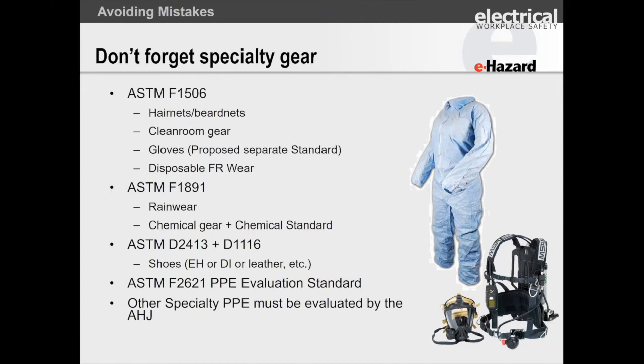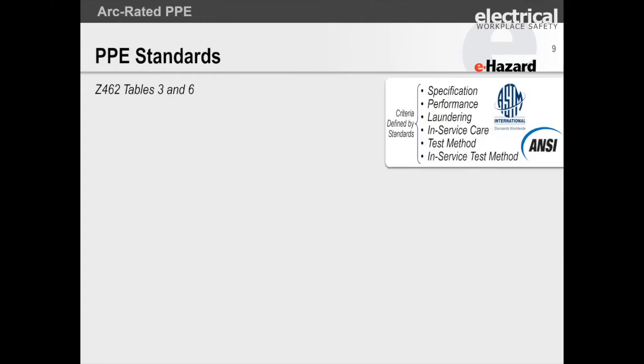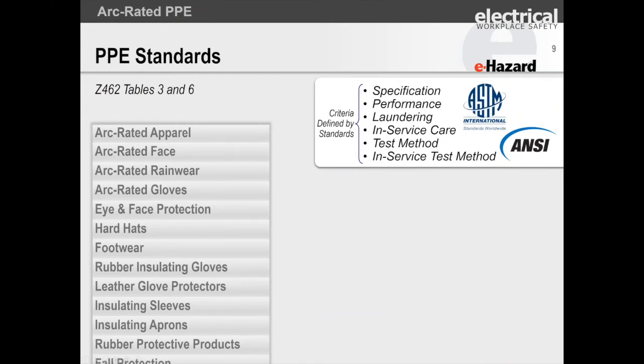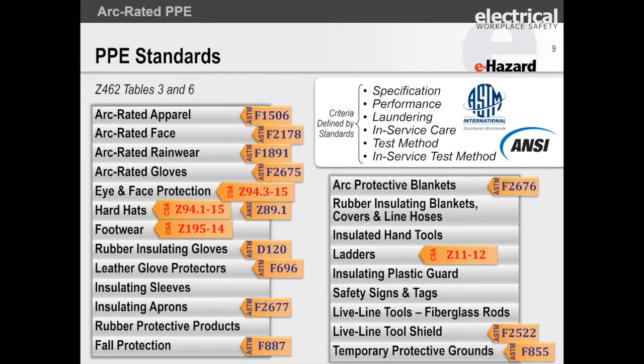It's important to make sure this gear doesn't increase the injury, and this is required for the authority having jurisdiction in 70E and Z462. There are several tables in Z462 and 70E that give the correct standards to use for your PPE. Don't trust anything not listed with the standards that are correct according to the standard.